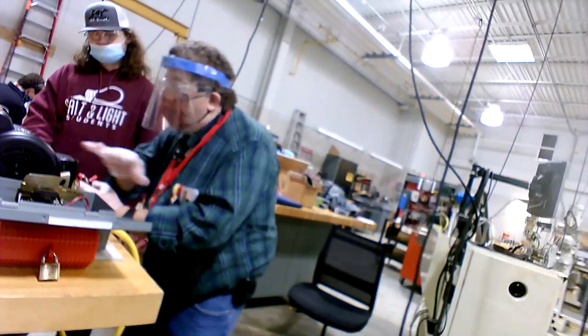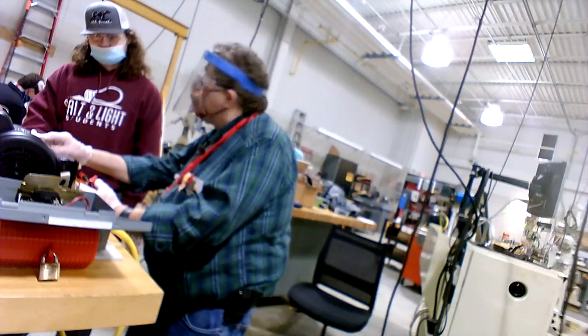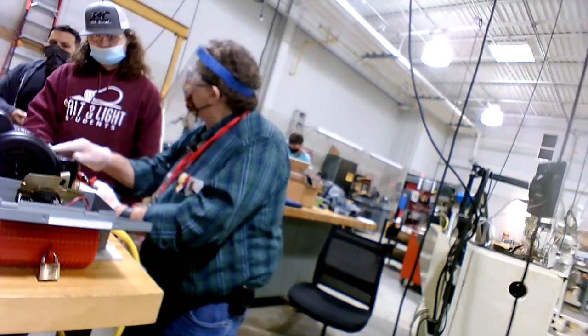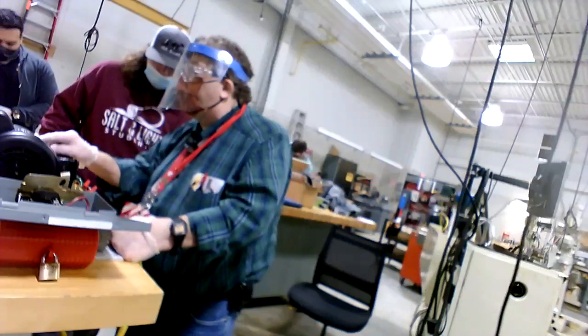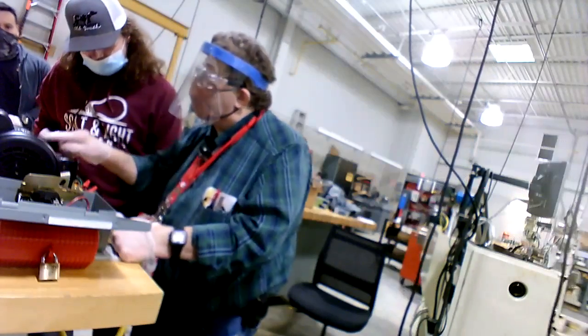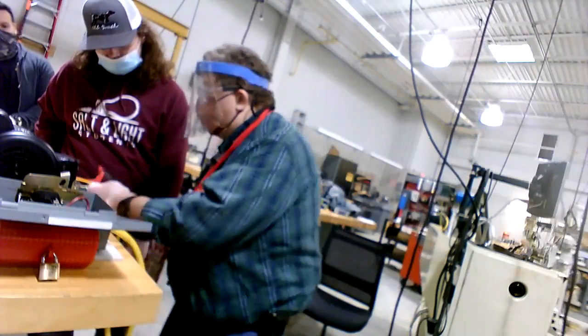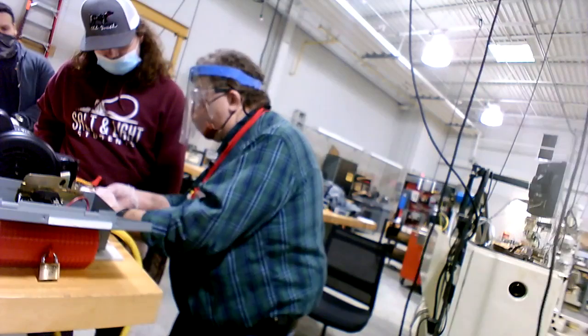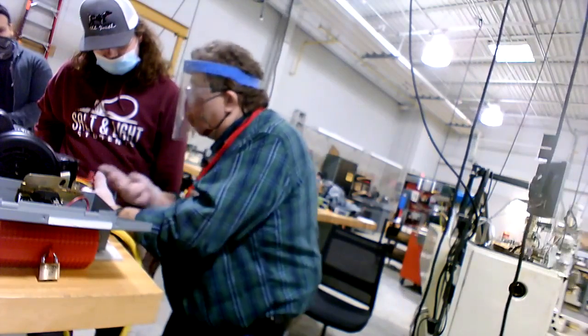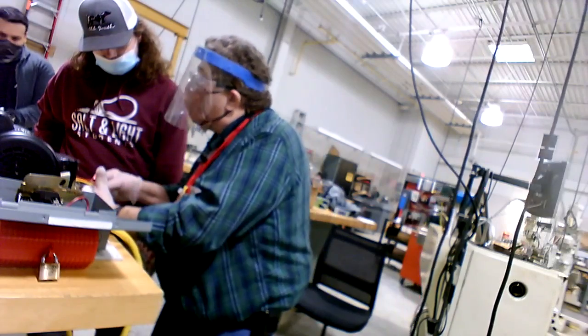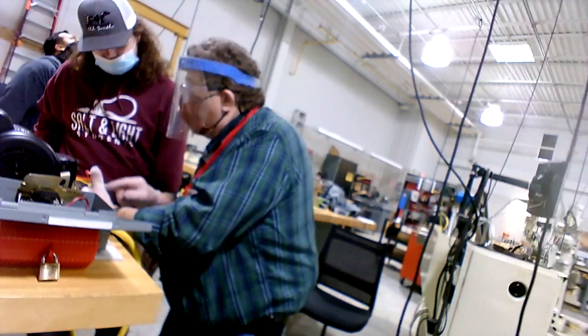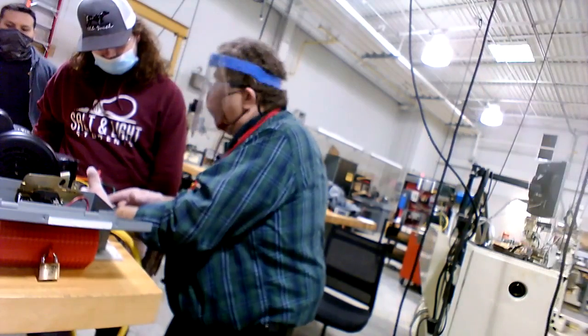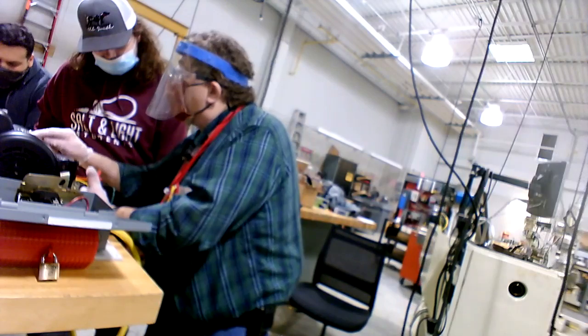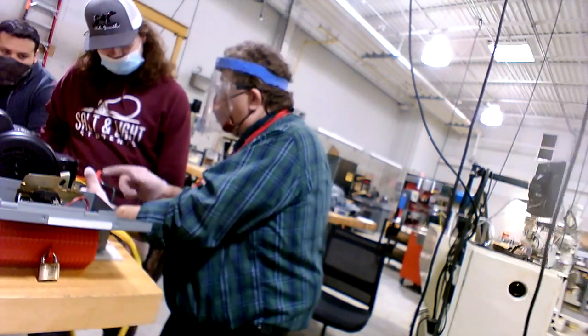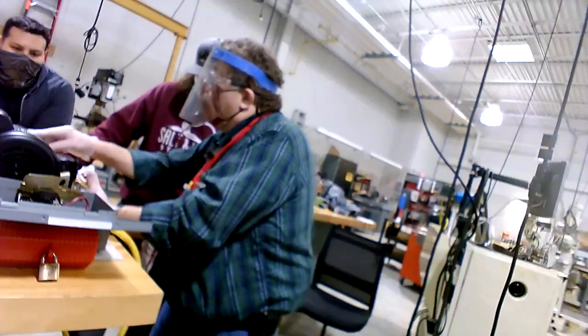Now, so this is the high voltage up there. I think did you go off of it? Yeah. On here, we're dealing with the high voltage on the 230 range. It's actually 208, and it's just high voltage. If you make your incoming line, your 1 and 2, and I don't even have these labels here. But line 1, and it doesn't even matter which one you hook up how. But line 1, pick one of these, it's going to go to blue only. Line 2 would go to yellow and black only. And then your orange, red, and white, it says insulate, they just go to wire up. They don't do these one line. So that's the high. Yeah.